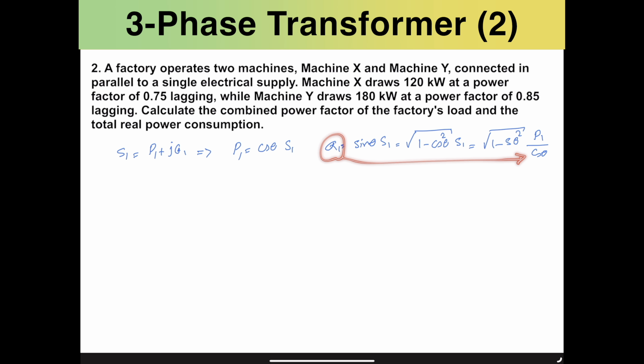So that is how Q is represented with all the given information. We have P1 as 120, cos theta as 0.75. If you plug them in, you get square root of 1 minus 0.75 squared, times 120 kilowatt, divided by 0.75, which gives around 105 kvar. That is the reactive power of machine 1. So machine 1, S1, can be represented as 120 k plus j105 kvar.